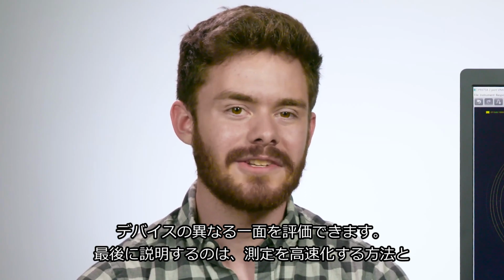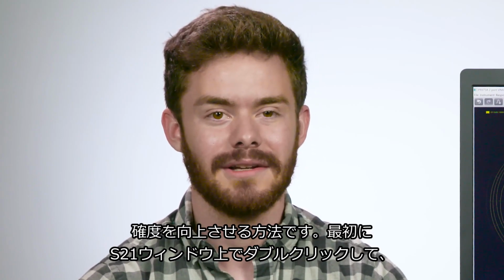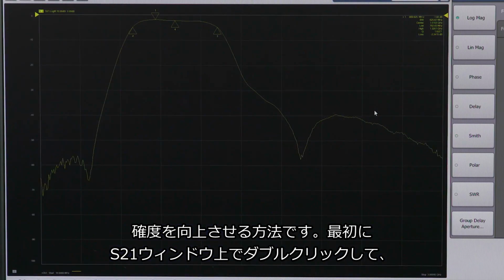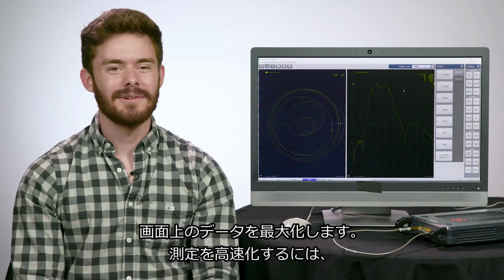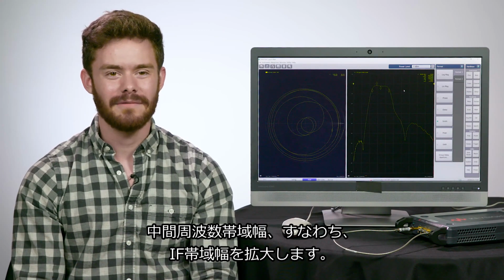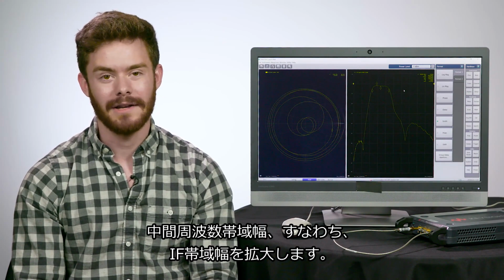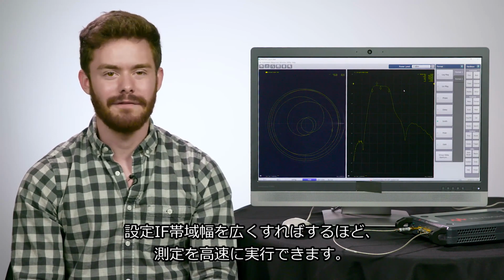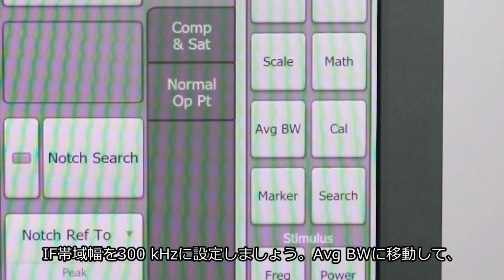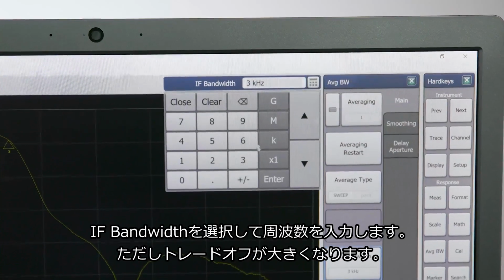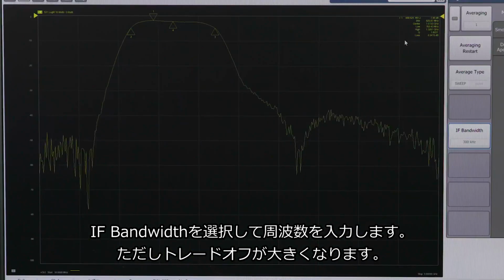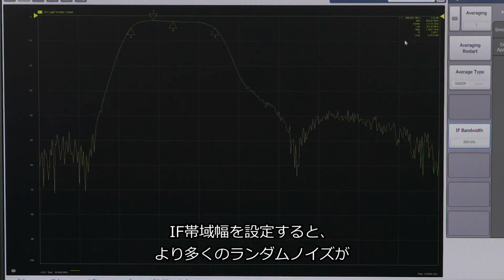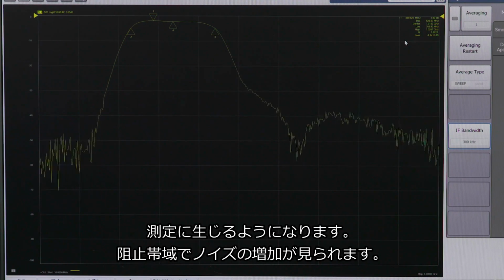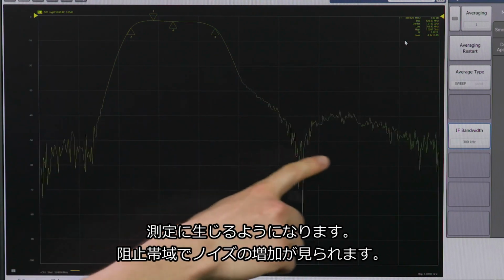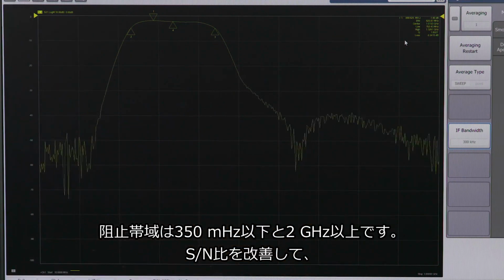Lastly, let's learn about how to speed up measurements and improve their accuracy. First, I'll double-click on the S21 window to maximize that on screen. In order to speed up the measurements, we need to make the intermediate frequency bandwidth, or IF bandwidth, wider. The wider the IF bandwidth is set, the faster the measurements can be performed. So let's set the IF bandwidth to 300 kHz by going to Average Bandwidth, IF Bandwidth, and enter that frequency. However, the trade-off is the higher the IF bandwidth is set, the more random noise will be introduced to the measurement. You can see that increased noise here in the rejection bands below 350 MHz or above 2 GHz.